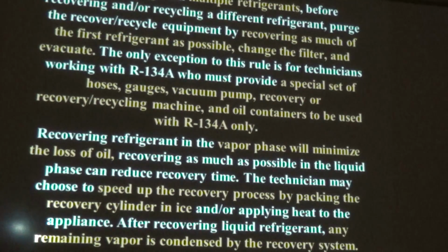When you're working with multiple refrigerants, this last part is what I want you to really highlight or pay attention to in your notes, because this is a test question. When working with multiple refrigerants, before recovering and/or recycling a different refrigerant, purge the recover-recycle equipment by recovering as much of the first refrigerant as possible, change the filter, and evacuate. This is the first part of the question. This is the answer right in here. The only exception to the rule is the tech working with R-134a, who has to use a special set of hoses and gauges for recovery. Recovering refrigerant in the vapor phase minimizes the loss of oil.